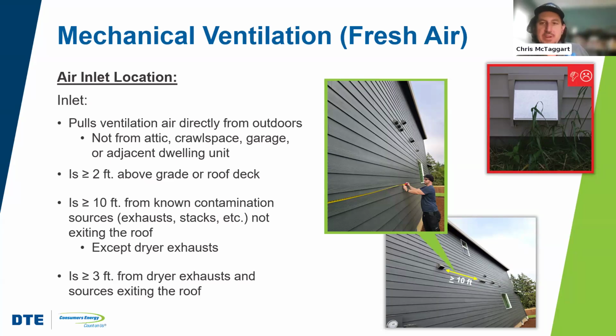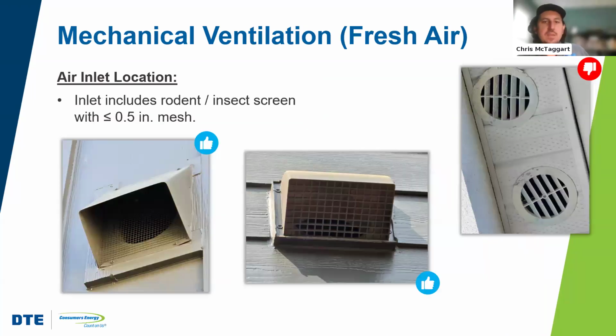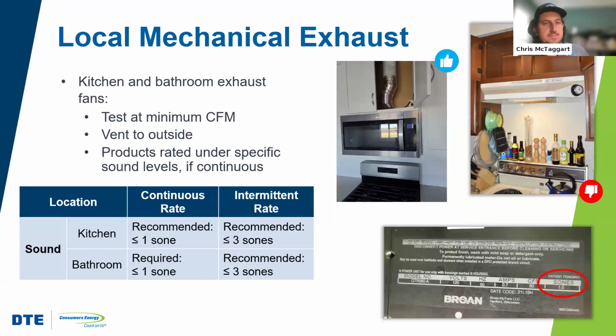So, if you're going to use either supply fresh air or balance with fresh air intake, there has to be some more thoughtfulness that goes into where you're placing these inlets. They also need to have rodent screens so as to make sure that they don't get fouled or allow vermin to make its way into the home.